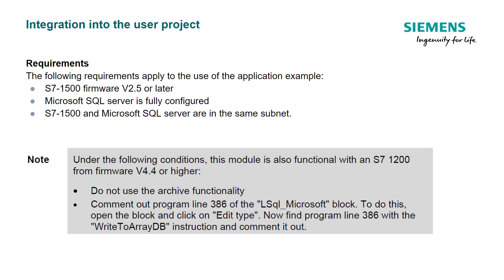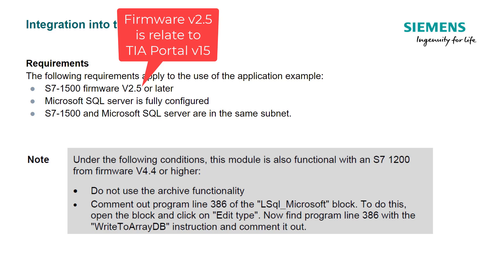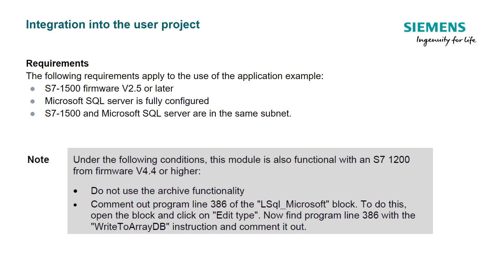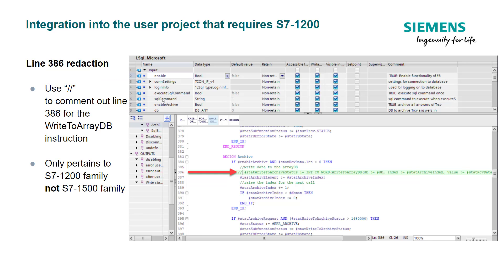The following requirements apply to this application example. The S7-1500 firmware must be version 2.5 or later. Microsoft SQL Server must be fully configured. The S7-1500 and Microsoft SQL Server must be in the same subnet. If you intend to use the S7-1200 with this library, this module is also functional with the S7-1200 from firmware v4.4 or higher. Note that v4.4 firmware is only available in TIA Portal v16. Do not use the archive functionality, and comment out program line 386 of the LSql_Microsoft block — specifically the WriteToArrayDB instruction — using double forward slashes. This only pertains to the S7-1200 family and not the S7-1500 family.